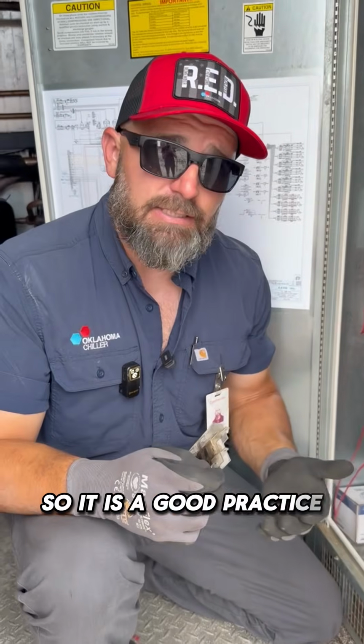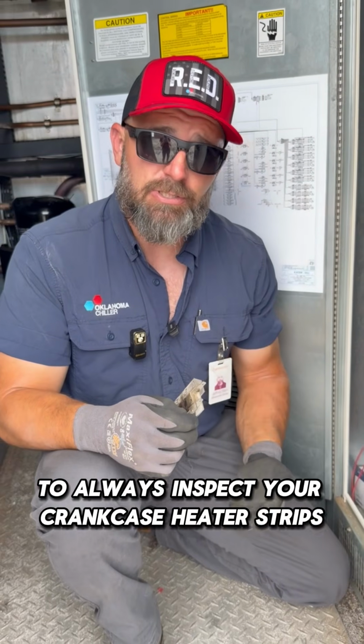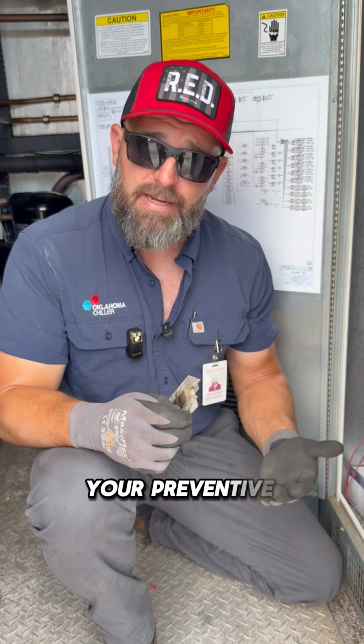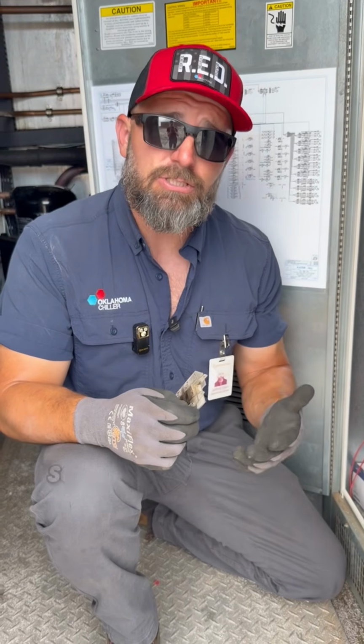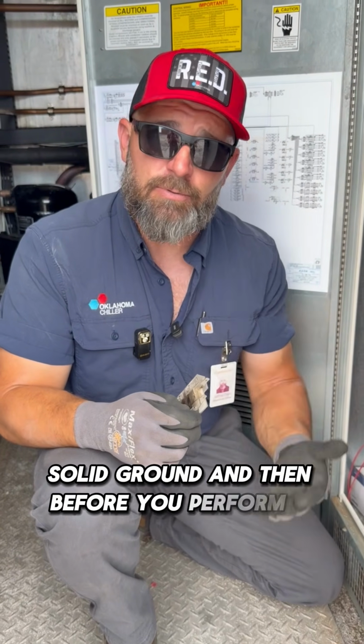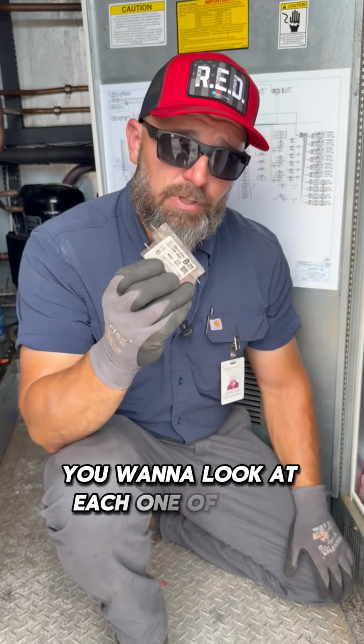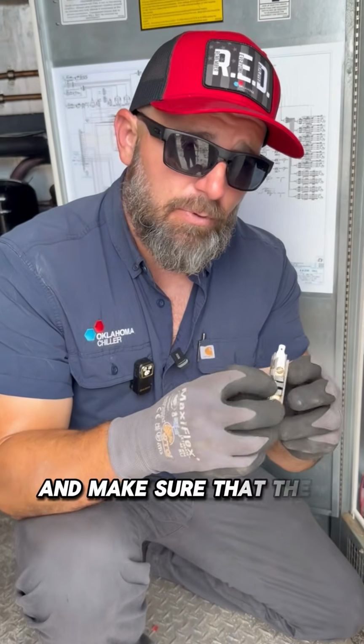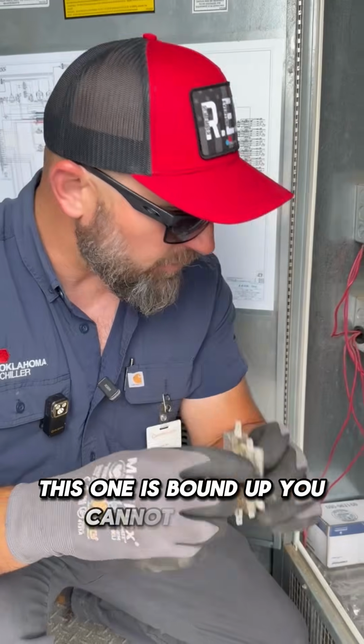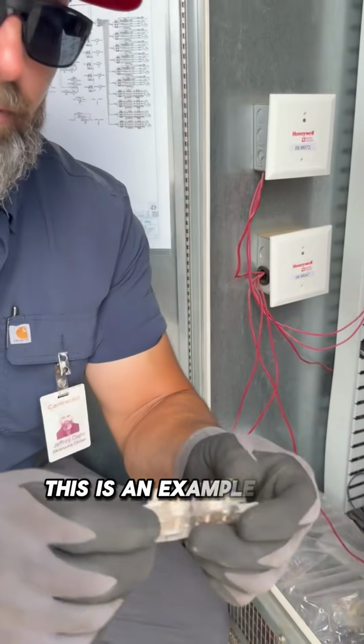So it is a good practice to always inspect your crankcase heater strips on your run-ins, on your annual preventive maintenance, to ensure that they have a good solid ground. And then before you perform a startup, you want to look at each one of these auxiliary relays and make sure that they move freely. This one is bound up, you cannot push it in. This is an example of a healthy one.